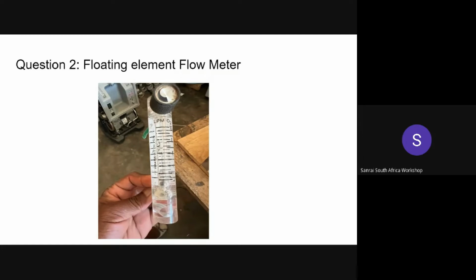So if you look on the screen, that's a floating element flow meter, which is mostly used in oxygen concentrators. Oxygen concentrators mostly use floating element flow meters that have a ball inside, as shown in the picture on screen. Oxygen provided by a concentrator is measured in LPM, which means liters per minute, for continuous flow.